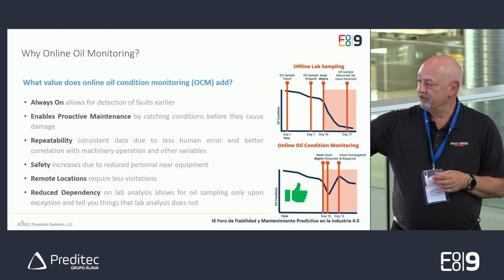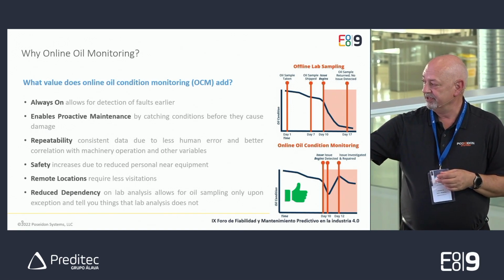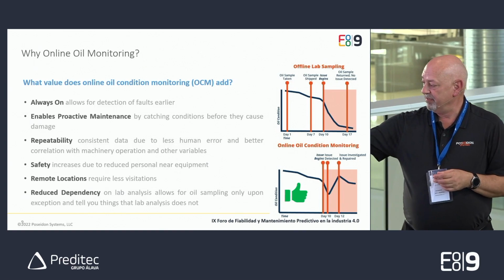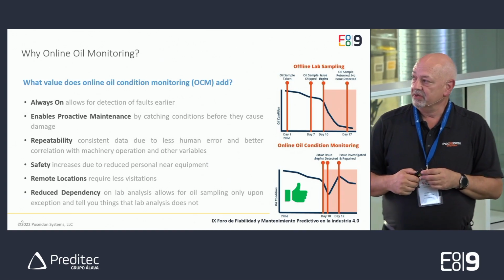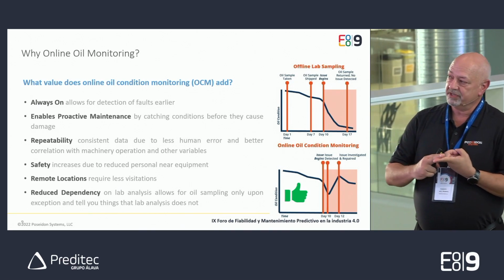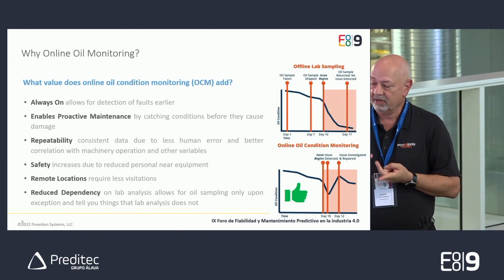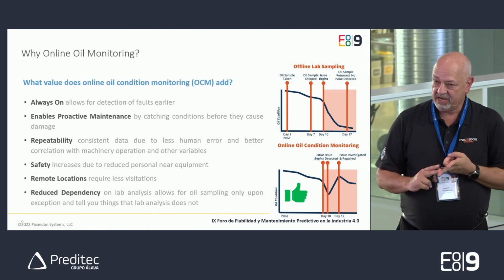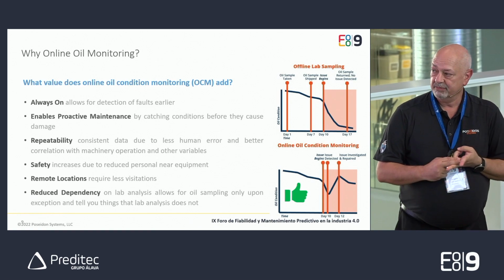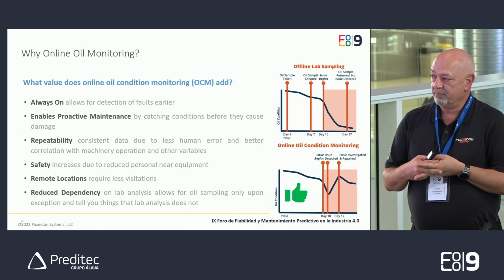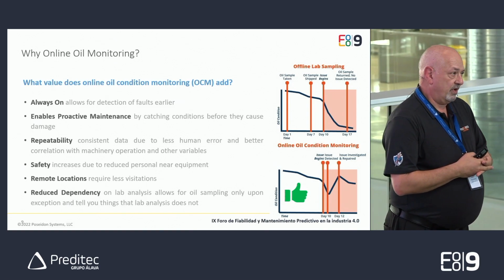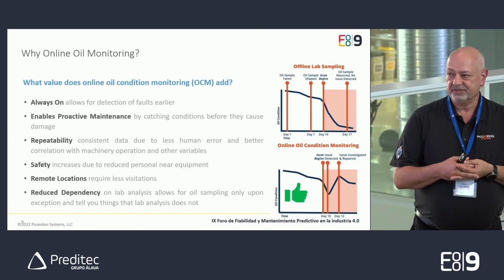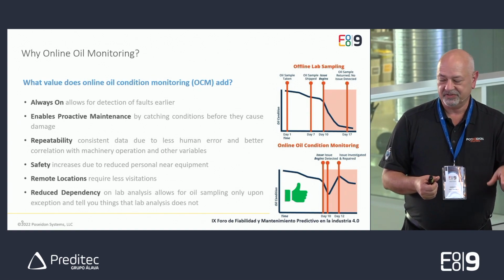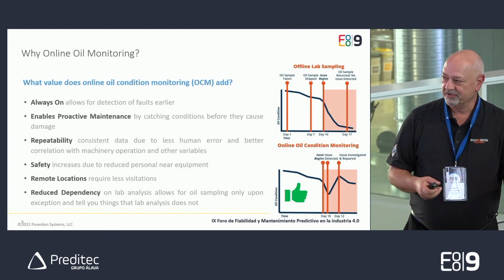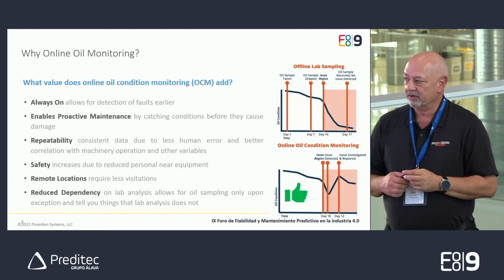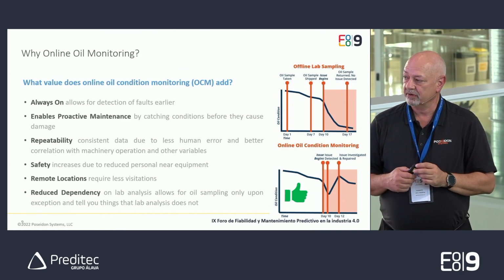Same situation with continuous monitoring. Issue begins, issues detected, issues investigated and repaired, and things are back to normal. So with online oil monitoring, it's always on, allowing for detection of faults earlier. It enables proactive maintenance by catching conditions before they cause damage. You get repeatably consistent data, whereas with oil samples, depending on who's taking the sample, where they're sampling, when they're sampling, where the sample's going, the data sets are much less repeatable, consistent.